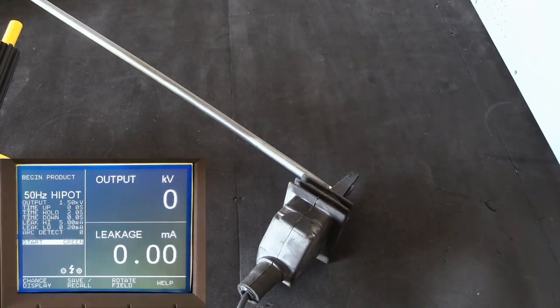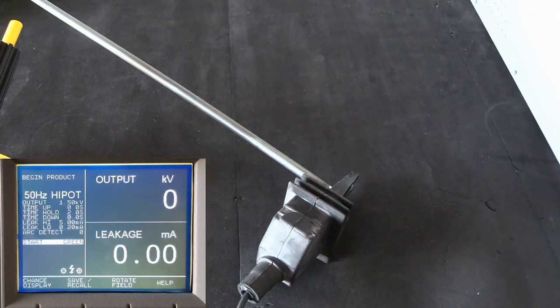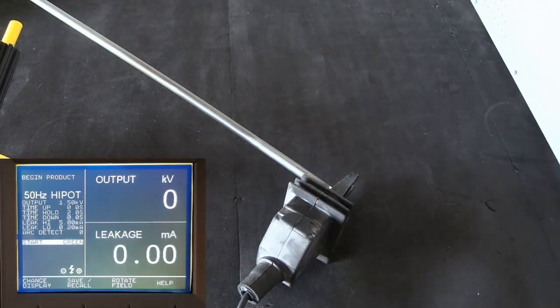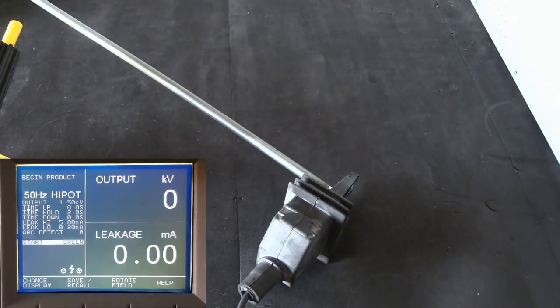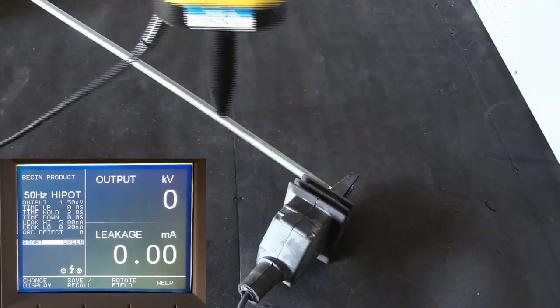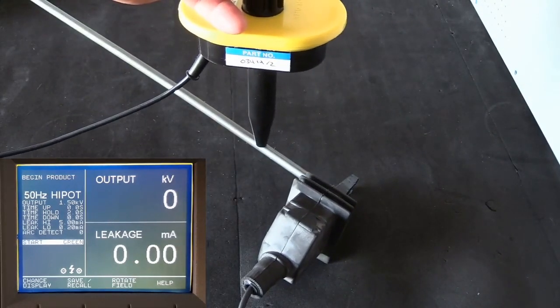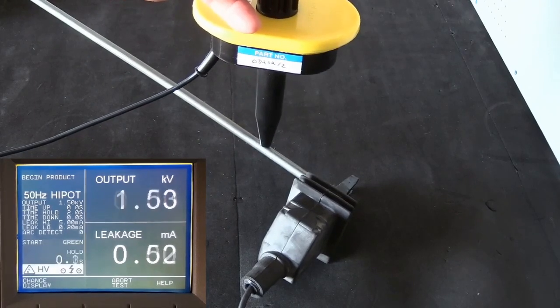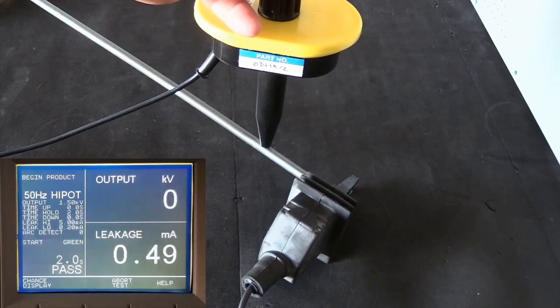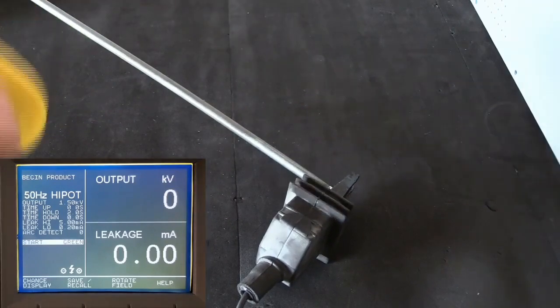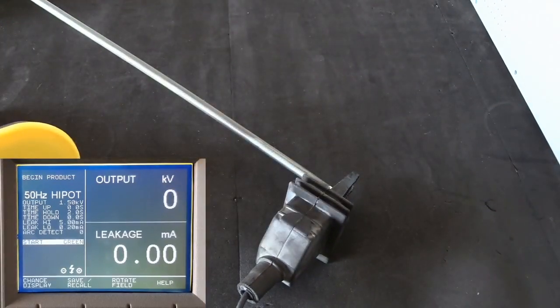So if we forget to put the clip on, we would expect to get no leakage, but we know we should expect some. So we've set a lower limit of 0.2. If for any reason it's below that, the test will fail, but hopefully the reading will come in between the upper and lower limits. So let's attach our probe and perform the test. And you can see the leakage was 0.49 milliamps, indicating a good test.